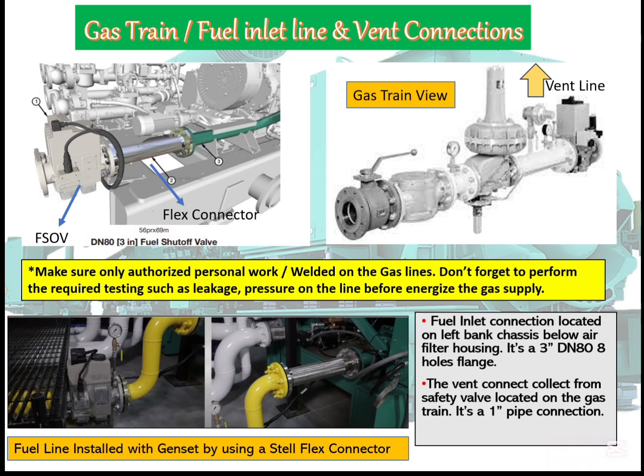Make sure that whenever we are working on the gas lines, it should be authorized personnel doing the welding work, so that the welding is very neat and clean, with no pinhole. Then before energizing the line, we should perform leakage testing, pressure testing, X-ray and other required testing according to your territories. Make sure we perform all those testing requirements before we energize the line with actual fuel.